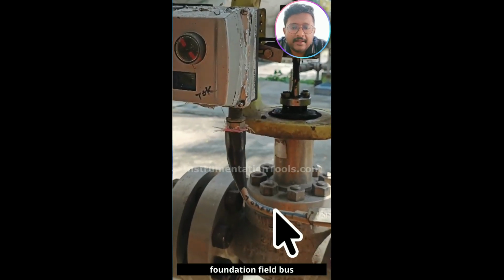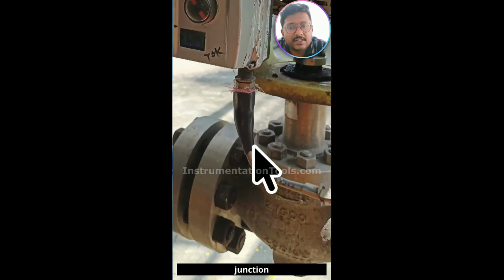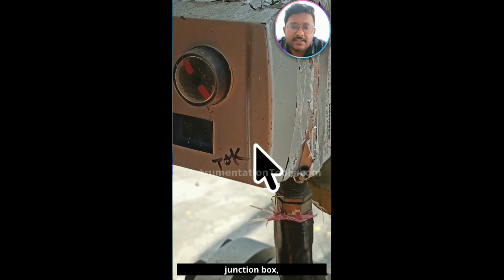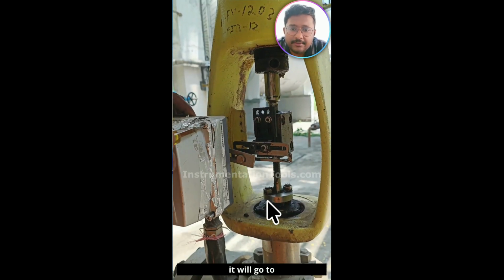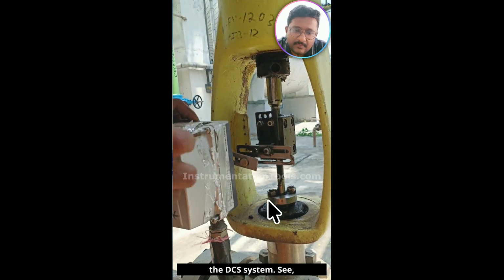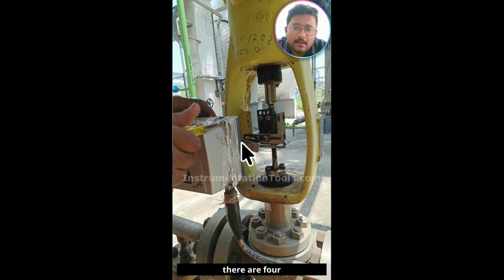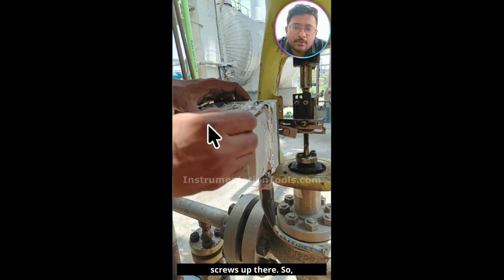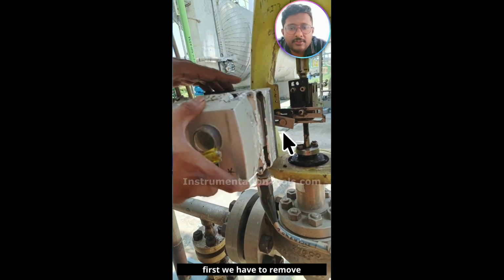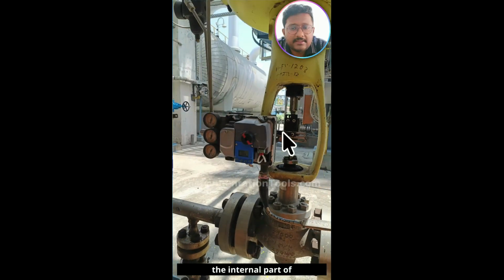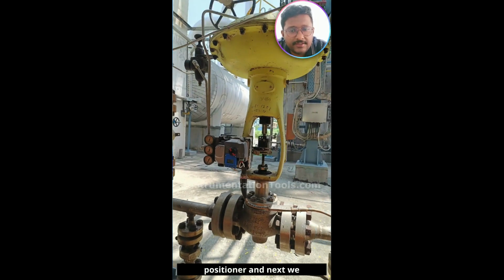This cable will be connected to a foundation fieldbus junction box, and from the junction box it will go to the DCS system. See, there are 4 screws. So first we have to remove the screws, and this is the internal part of the valve positioner. And next we have to connect the HART communicator across these terminals.